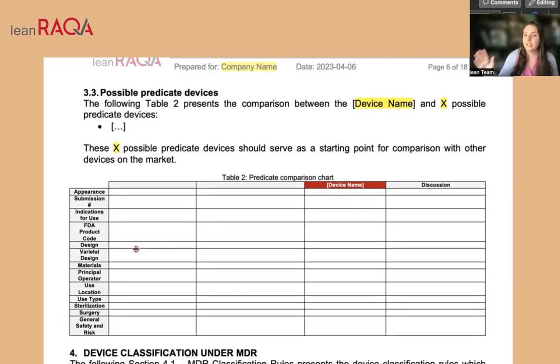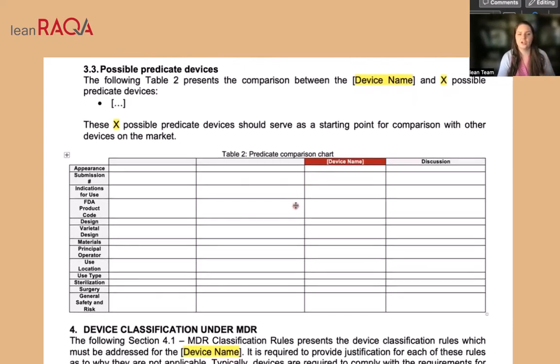You can use it directly in a 510K if you're starting to do your predicate comparison, because what FDA is going to be really looking for is how similar are you to your competitor or other existing technology, and are there any concerns about safety or efficacy that aren't being addressed? So you can start to fill in directly what you find from those databases into this document.